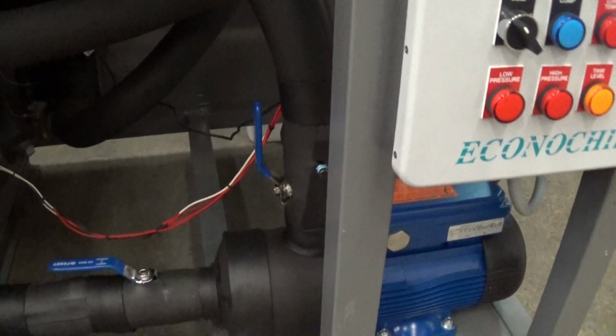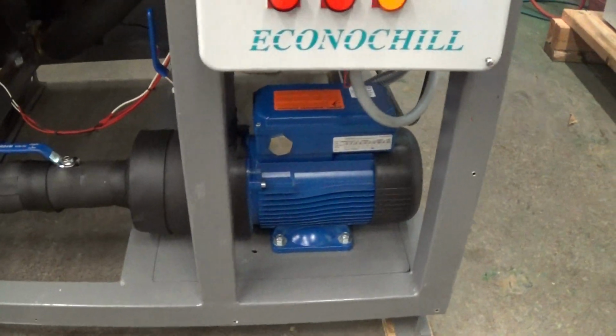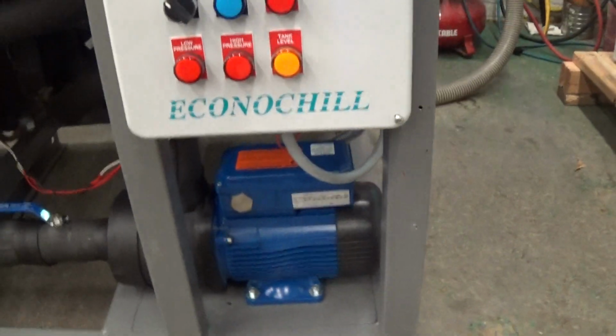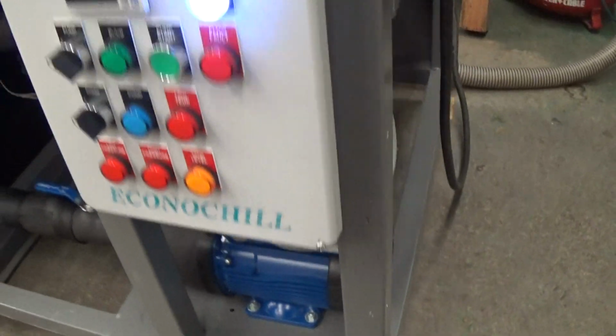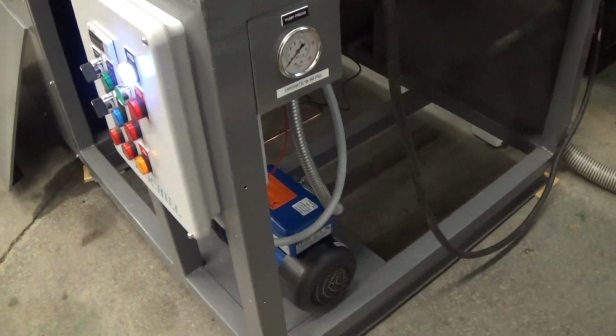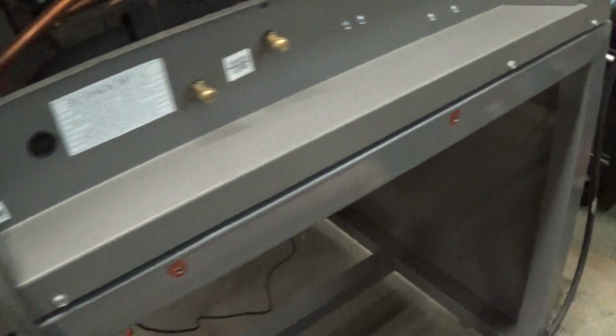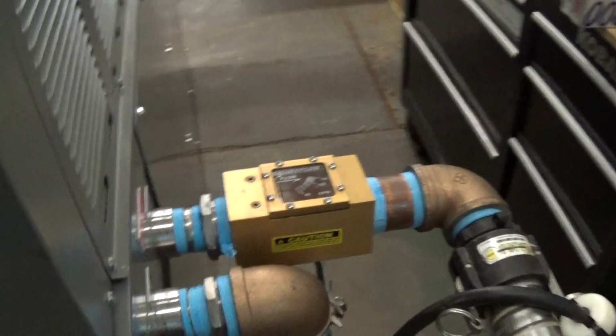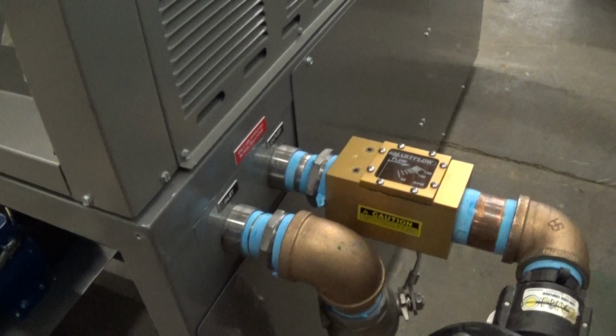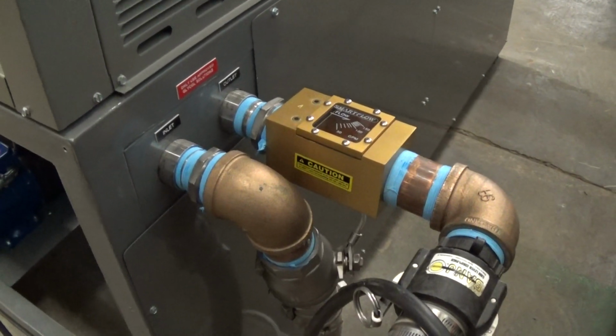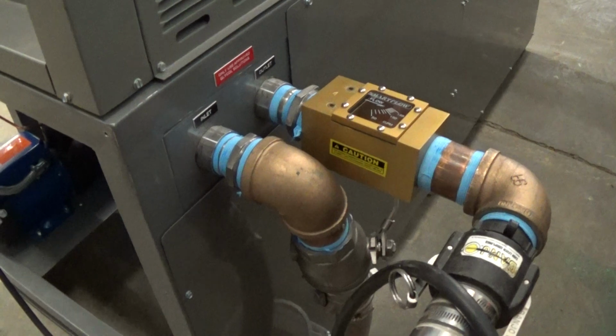The direction of flow is we draw from the tank. The pump draws from the tank, then we go out to the heat exchanger first. Then we go from the heat exchanger out to the process. We like doing it this way, especially if it ends up in a brewery application, or if it goes to multiple processes, because we satisfy the pressure demands of the heat exchanger first, and we do not require any particular type of pressure of the return flow coming back to the chiller at all. It's effectively returning under zero atmospheric pressure, if you will, back to the chiller.